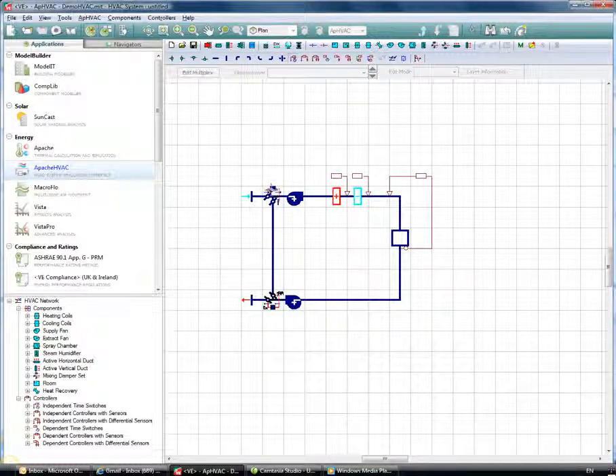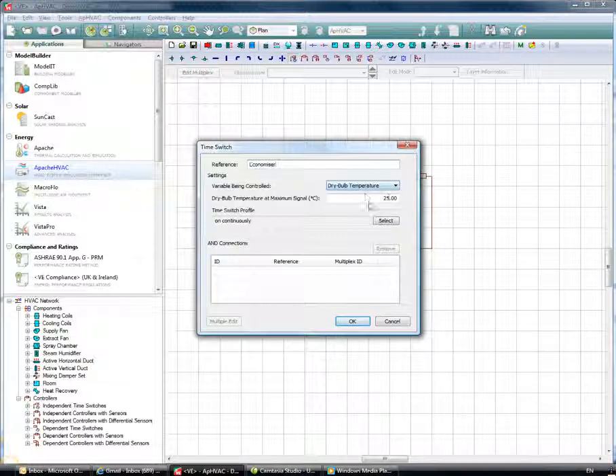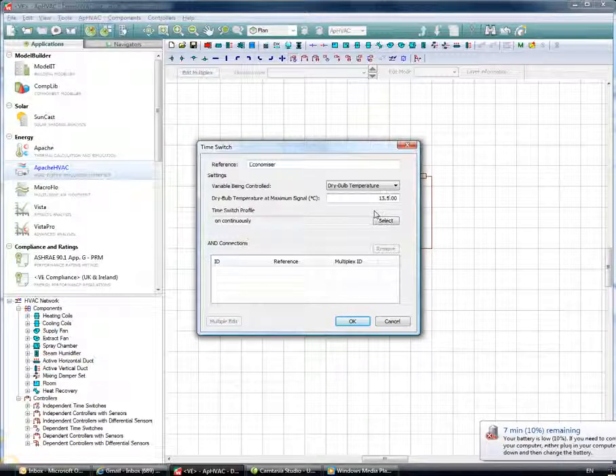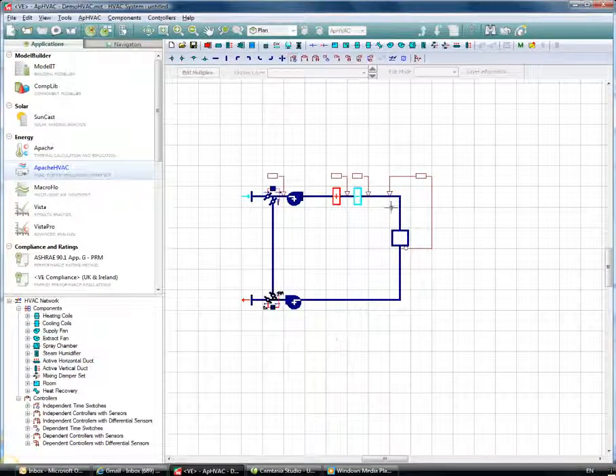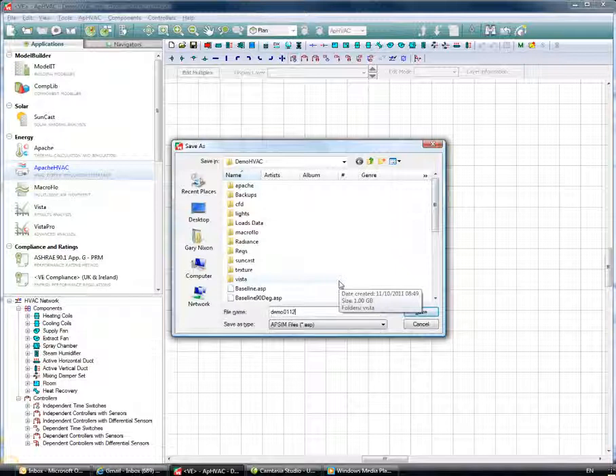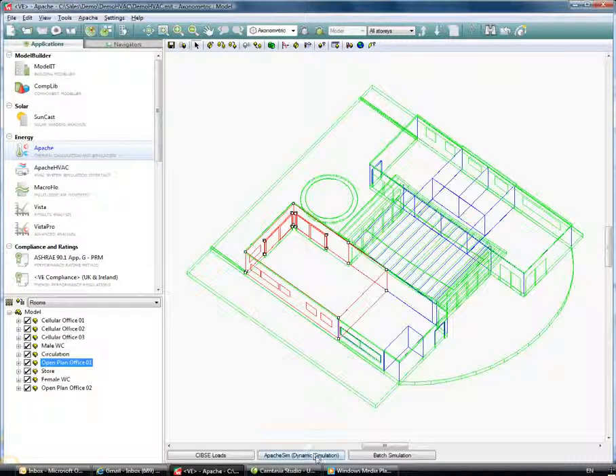Next, I'll set up a controller for the outside air economizer — a time switch to control the damper. I'll set a target mixed air temperature of 13.5°C, calling it 'Economizer Dry Bulb Temperature'. The controller will modulate the damper mixing outside air and return air to get as close as possible to that target mixed air temperature of 13.5°C. Clicking OK, all components are in place, and I'll save this file as 'Demo 12'.